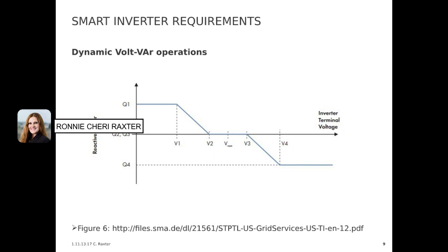This setting is the dynamic volt-var operations. This also has to be activated. In this instance, the grid voltage would dictate the quantity of VARs that the inverter would inject or consume. This is particularly beneficial in locations with high DER penetration because it reduces voltage rise, which is associated with high DER penetration. By injecting or consuming VARs, the DER inverter is helping maintain the grid voltage quality. And looking at this in the long term, they're also allowing more DERs to be installed in that specific location, and are also reducing the potential of nuisance tripping that would be caused from high DER penetration.